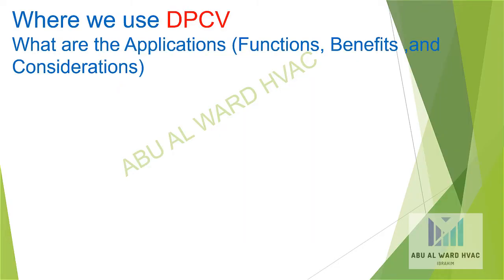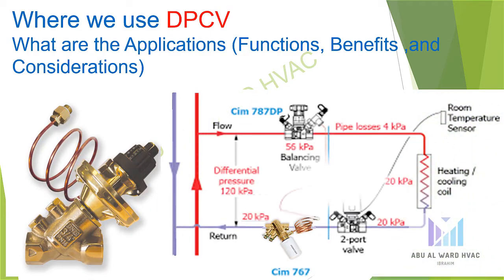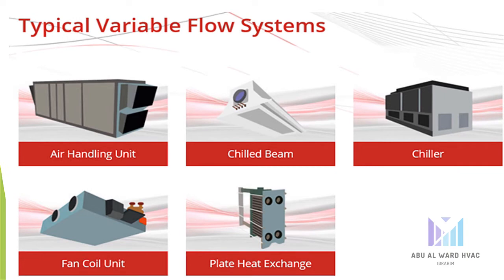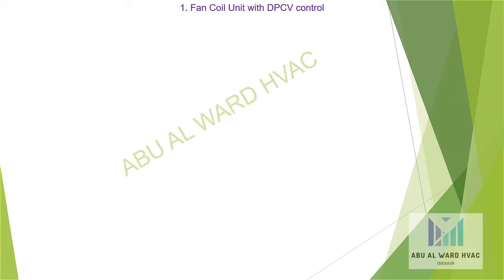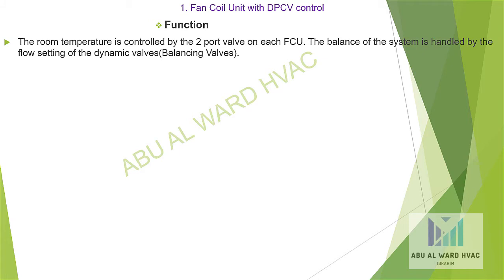Where do we use the DPCV? Applications include air handling units, chilled beams, chillers, fan coil units, and plate heat exchangers. For fan coil unit DPCV control, the function is: room temperature is controlled by a two-port valve on each FCU, and the balance of the system is handled by the flow setting of the dynamic balancing valves.